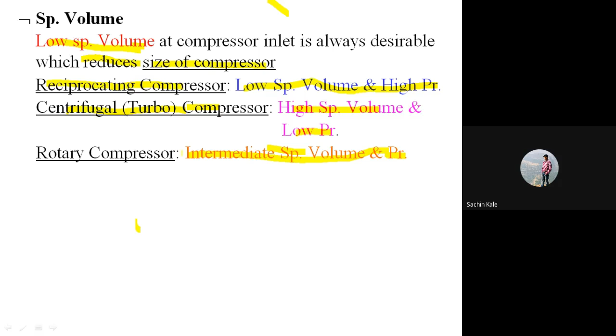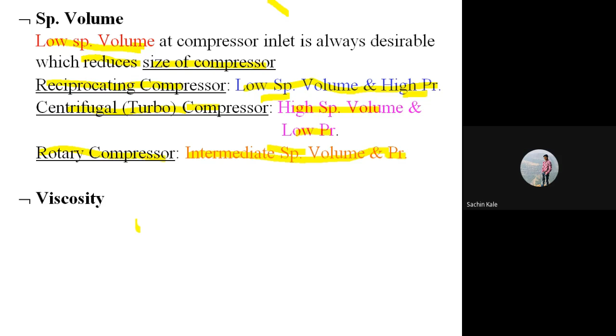Then the second point is related to viscosity. Viscosity is nothing but resistance to its own flow. If higher viscosity is there, then the refrigerant circulating through the VCRS system will not circulate with proper speed. That means you require maintaining a higher pressure range. So while selecting the refrigerant, depending upon viscosity, you have to select a refrigerant which has lower viscosity. Why lower viscosity? Because lower viscosity will reduce the pressure drop.